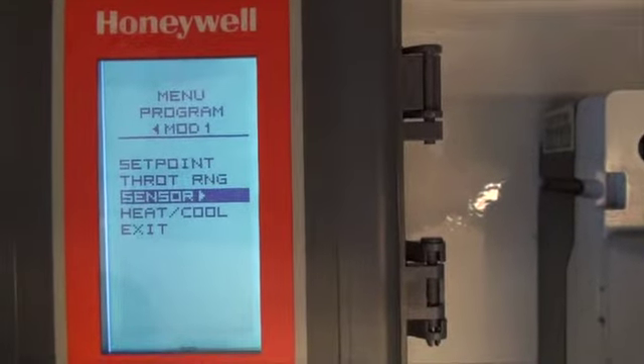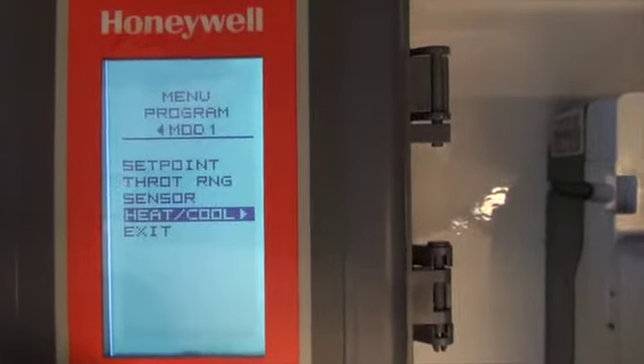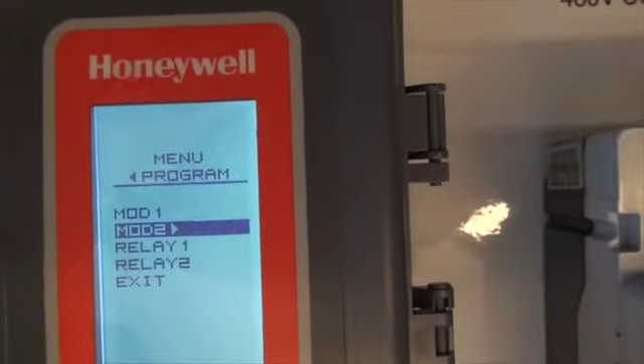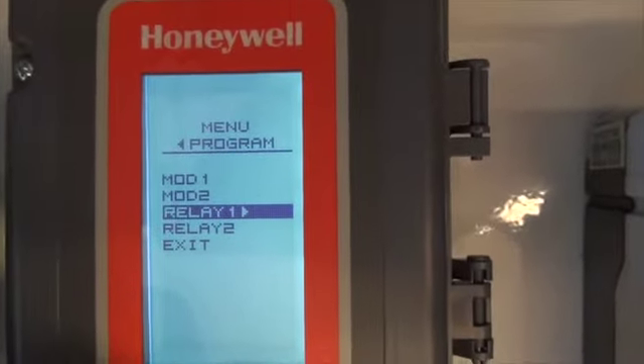So I press the right arrow key again with the sensor, which is sensor A, and of course it's got to be in the cooling mode. I'm pressing the right arrow key to go down, and then I exit the modulation. Okay, now mod 2 we're not using, so I'm going to go right past it, because that allows you to have a second modulating output, using the down arrow to go down past it.